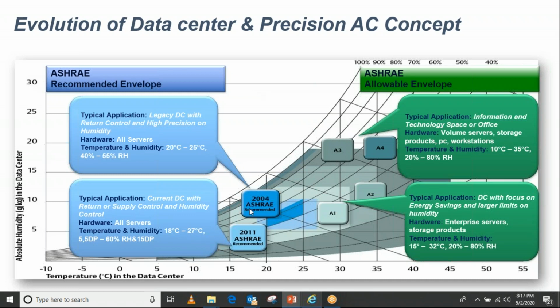So the installed capacity, installed number of units comes down, the efficiency improves, the power consumption reduces drastically, the kilowatt per TR ratio comes down drastically. So this overall makes a huge difference from this 2011 guidelines.